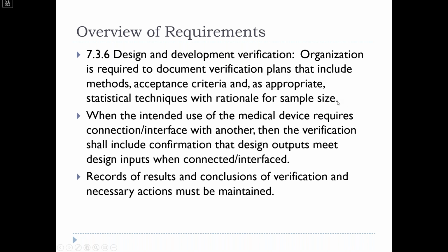7.3.6 talks to design and development verification. The organization must document verification plans that include the methods to be used, what the acceptance criteria are, and if appropriate, statistical techniques with rationale for sample size. Are we looking at every device or a sampling of the devices?